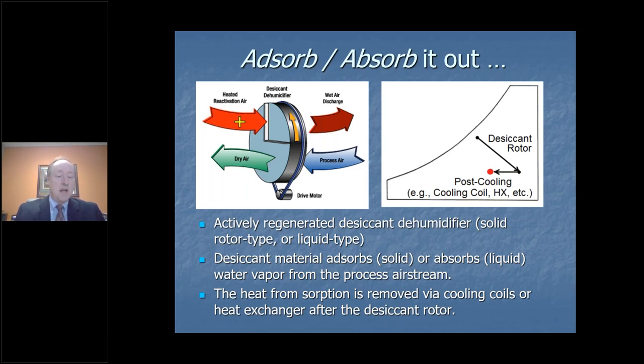Warmer because we pick up a lot of latent heat of fusion right there. Plus, we pick up a little bit of heat from the fuel that we use for the reactivation of that wheel. This is what it would look like in the psych chart. If you're starting at this point in your process, you go through the wheel, you are actually going from left to right, you're warming it up, but you're also going from up here to down here, so you're drying it out. And then at this point, you'll need to do some type of post-cooling or cooling after the wheel, and that's where we get the sensible cooling right here.